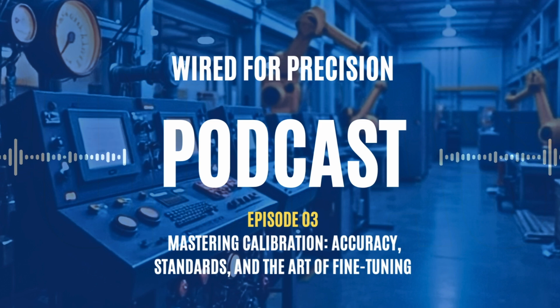2. Follow a multi-point check. Don't just calibrate at one value, test at multiple points across the range, typically 0%, 25%, 50%, 75%, 100%. This helps identify linearity or hysteresis issues. 3. Zero and span adjustments. When necessary, adjust both the zero or offset and the span or gain to bring the device within spec. Some transmitters allow digital trimming using HART communicators or field calibrators.